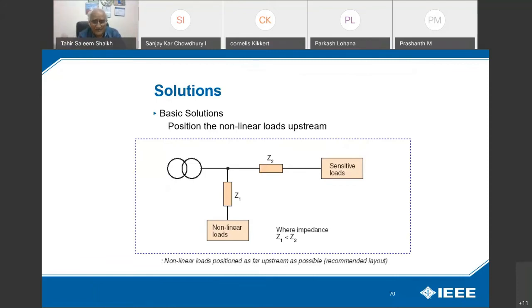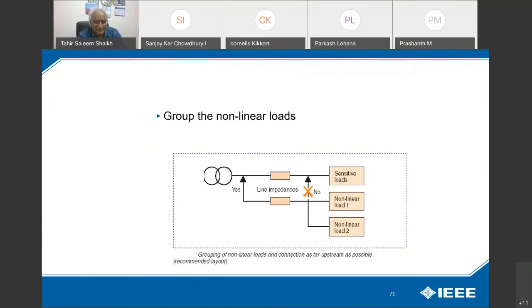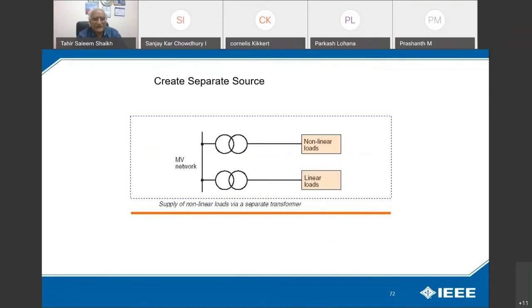So this is one solution, that you position the non-linear loads upstream. Then group the non-linear loads: you will have a separate bus bar for non-linear loads and a separate bus bar for sensitive loads. This is a general practice. The third would be to have a separate source for non-linear and linear loads, which I have seen in Karachi, a problem in a foundry. In a foundry, I found this phenomenon with the induction furnace. They connected the non-linear load and linear load on a single bus bar. The source is 11 kV, the medium voltage, and there was a lot of problem. So they had to separate the source of power with two sources, and then the non-linear loads have a separate panel and the linear loads have a separate panel.